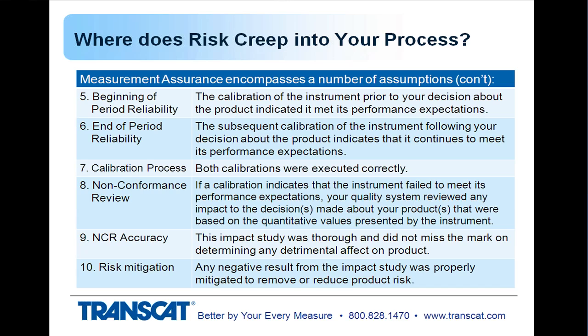Following the calibration, your nonconformance review. If your instrument failed to meet its performance specs, then your quality system probably has a review process in place that evaluates whether that had an impact to the decisions being made about the quality of your product, because that changes the quantitative values that you're relying upon.